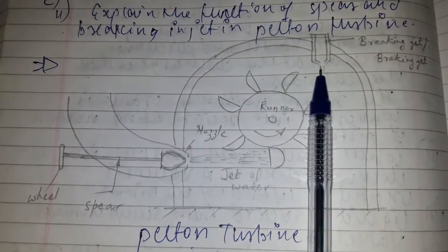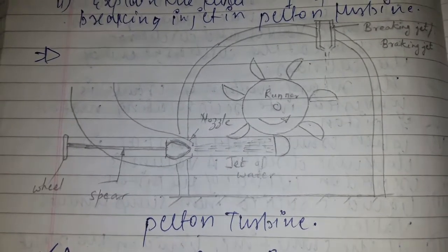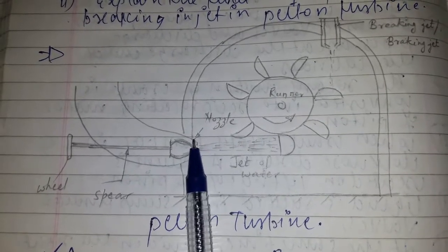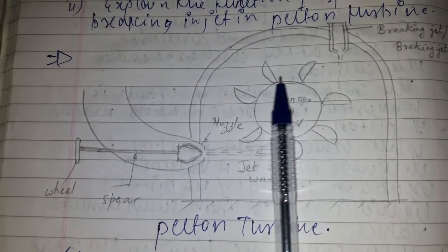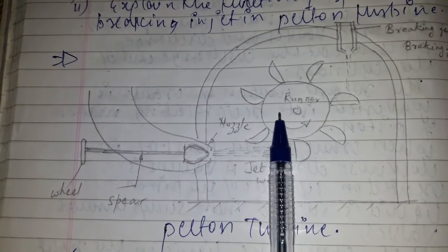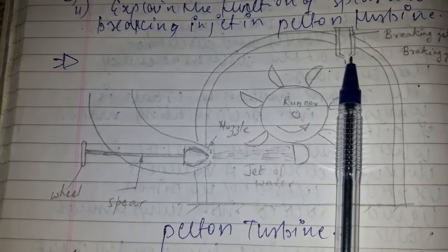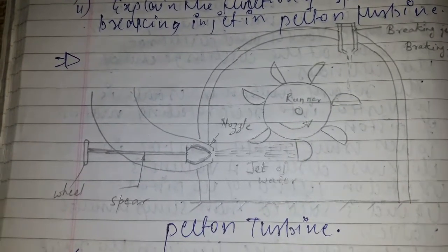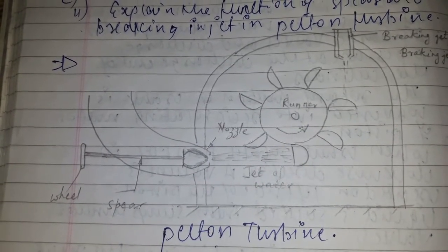Regarding the function of the braking jet: when the turbine is brought to rest, the nozzle is completely closed by pushing the spear forward. However, the runner continues to rotate due to inertia for a considerable period of time. In order to bring the runner to stop in the shortest time, a small nozzle is provided which issues a water jet that falls on the back of the bucket, acting as a hydraulic brake for reducing the speed of the runner.